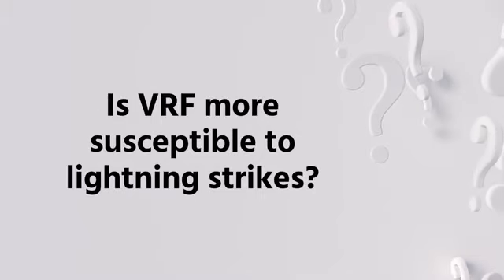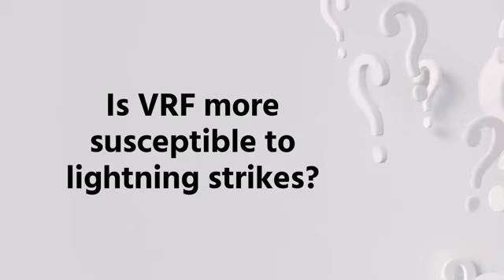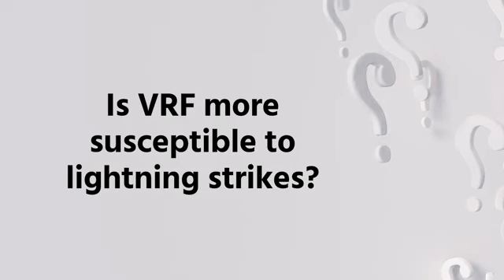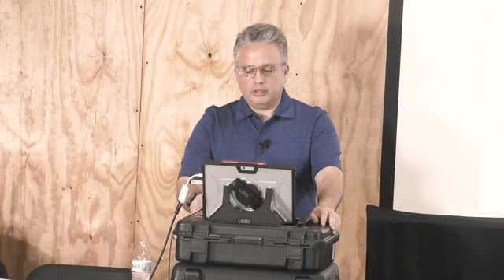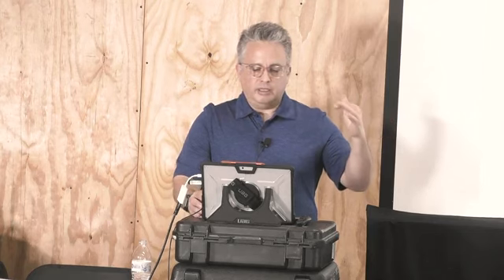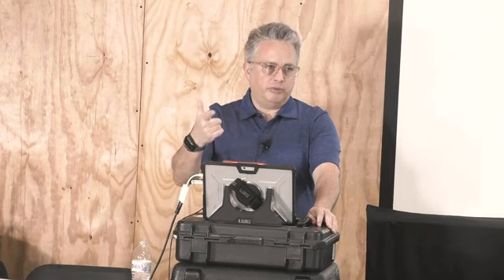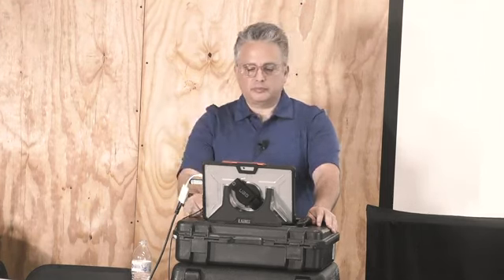Question? Sir? With all this interconnecting copper and electronics, do you have to worry about lightning strikes? Always. But more than normal? No. Florida has the most lightning in the US. I've worked on 2 hotels with lightning strikes, and there is no rhyme or reason what happens to the components in a lightning strike. This particular project had 8 systems, so 8 outdoor units, and it's a 4-story hotel, and every room had either nothing wrong with it or something different wrong with it. It took that contractor 2 months to fix it. They had to shut down for about 6 weeks.